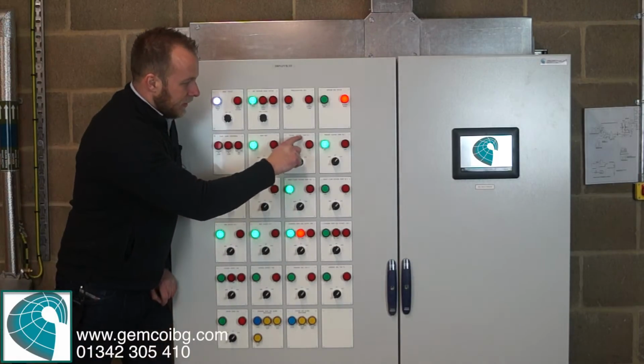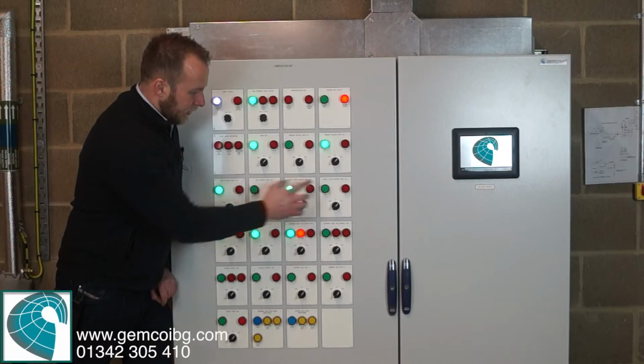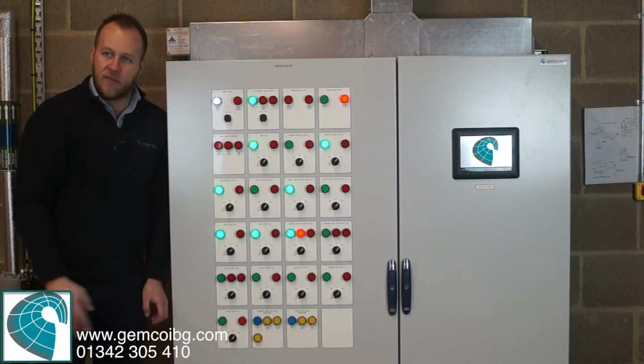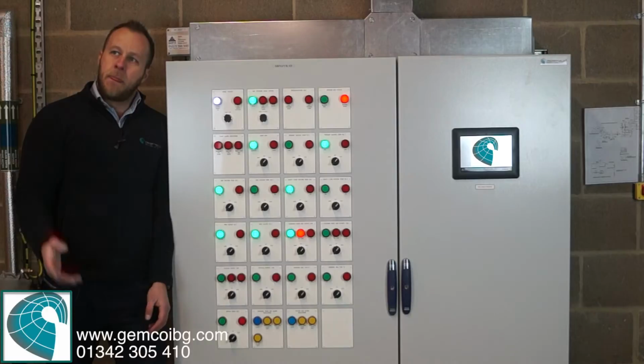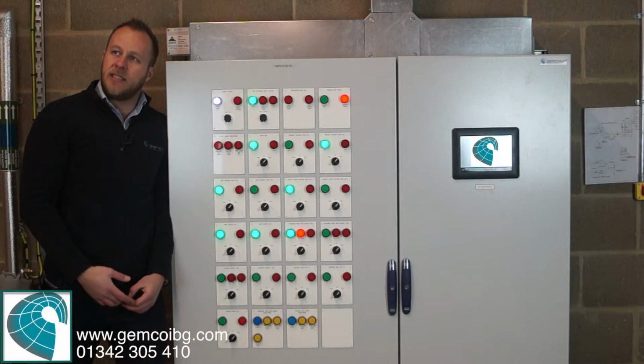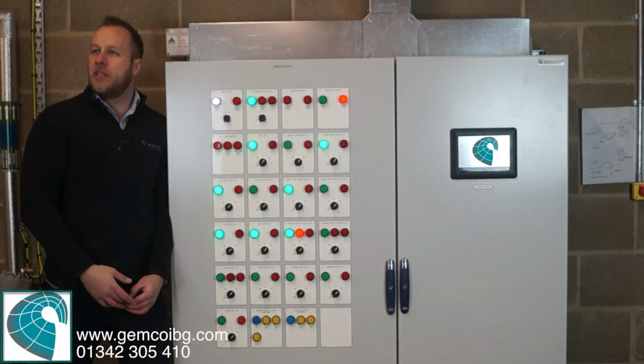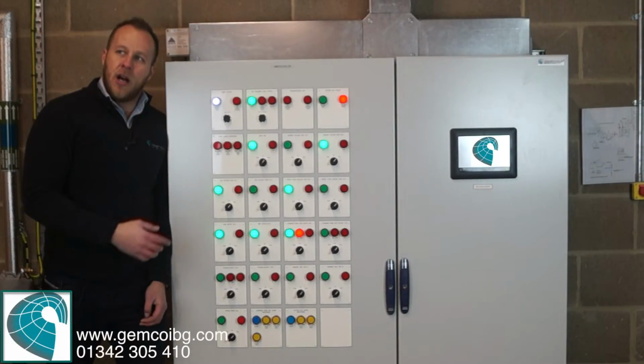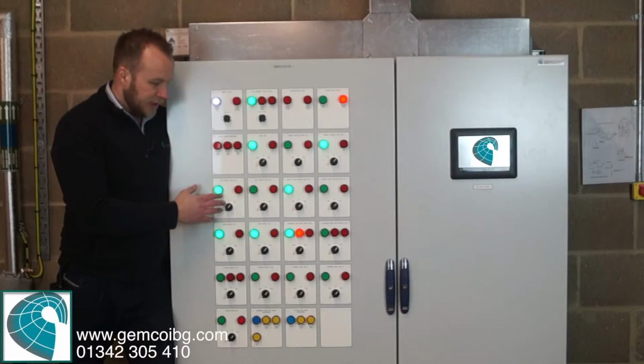You'll notice that there's 1, 2, 1, 2, 1, 2. Only one pump should ever be running at any one time. And it will tell you, it indicates on the pumps there, you can see one's in stop and one's at whatever the watts is at the time. Okay? Only one should ever run at a time. The reason is because they're the same pump.